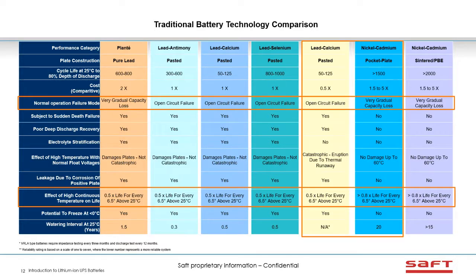As far as high temperature goes, if you increase the temperature above 25 degrees, 6.5 degrees Celsius, you're essentially cutting the life in half of a lead acid battery, versus you're basically still at 80% of what you would expect the life to be with a nickel cadmium battery. So much more resilient to high temperature applications and maintaining its long life.